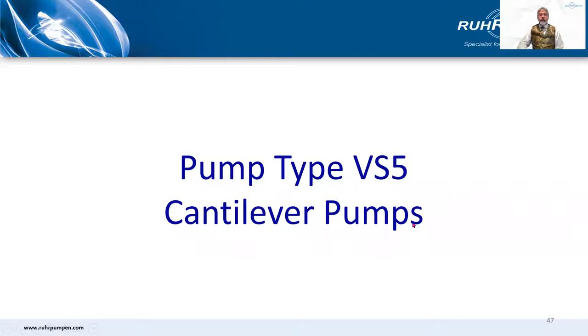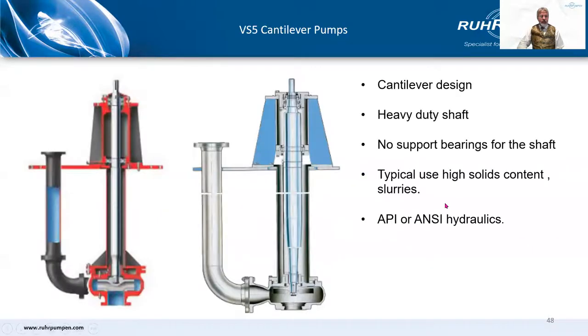Moving on briefly to the VS5 cantilever pump — not too much to say here. You don't come across them very often. They have a heavy duty, self-supporting shaft — a big, thick, heavy shaft instead of the fragile thin diameter shaft on the VS4. No line shaft bearings. They're typically used in high solids content service, slurries. This is a Flowserve image on the left and a Sulzer one on the right. There hasn't been the demand for Ruhrpumpen to actually develop one of these.